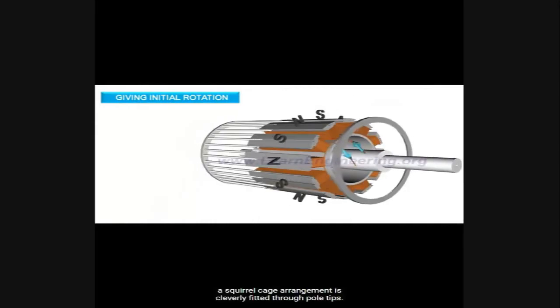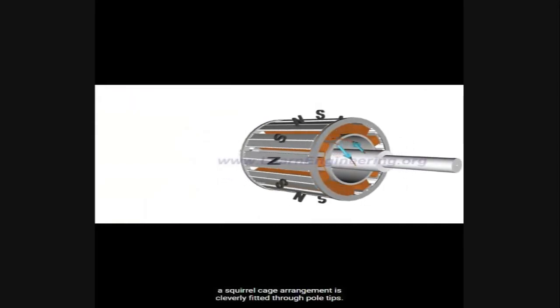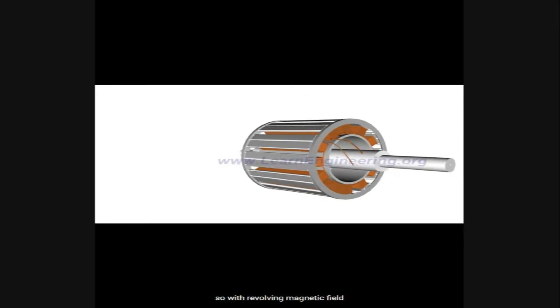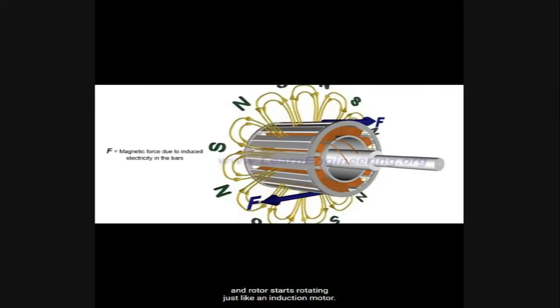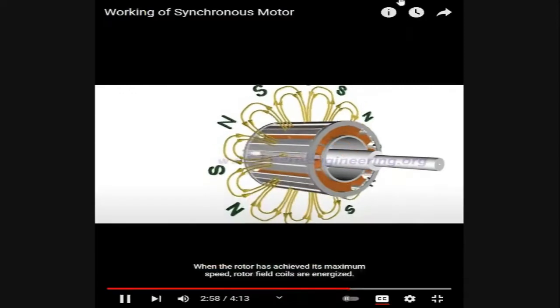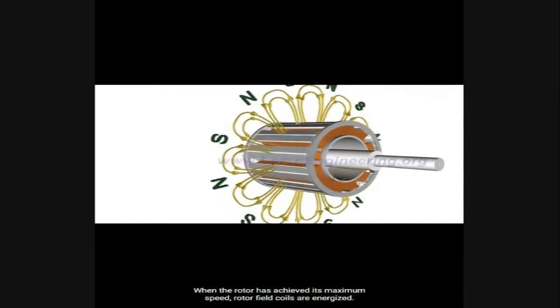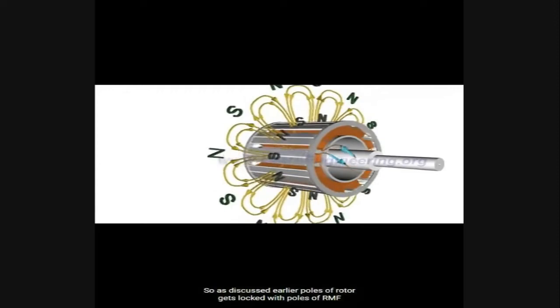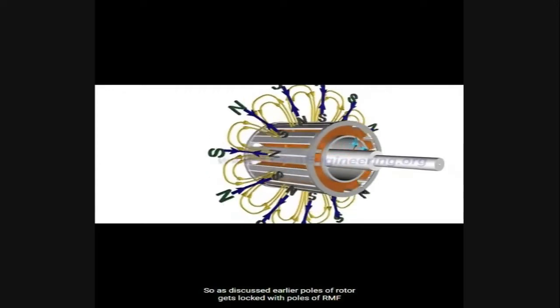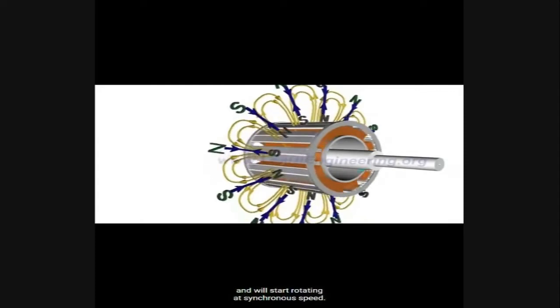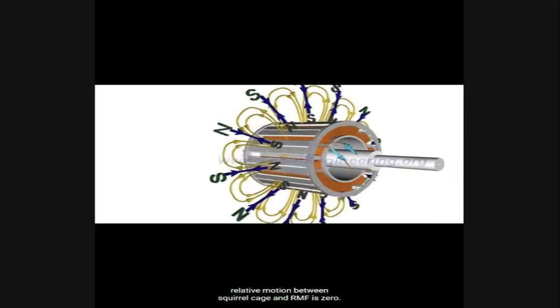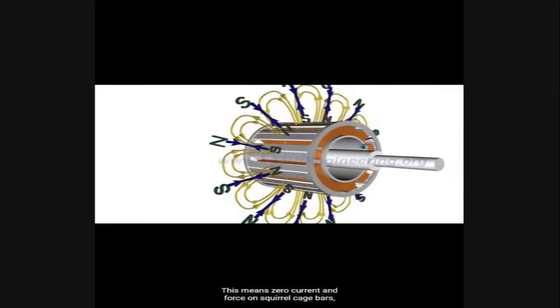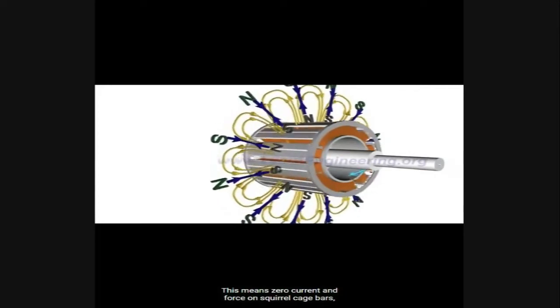To make a synchronous motor self-starting, a squirrel cage arrangement is fitted through the pole tips. At starting, the rotor field coils are not energized, so with the revolving magnetic field, electricity is induced in the squirrel cage bars and the rotor starts rotating just like an induction motor. When the rotor achieves its maximum speed, the rotor field coils are energized and the poles of the rotor get locked with the poles of the RMF, rotating at synchronous speed. At synchronous speed, relative motion between the squirrel cage and RMF is zero, meaning zero current and force on the squirrel cage bars.